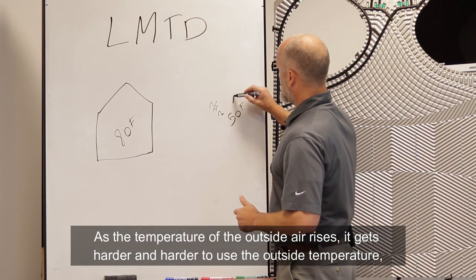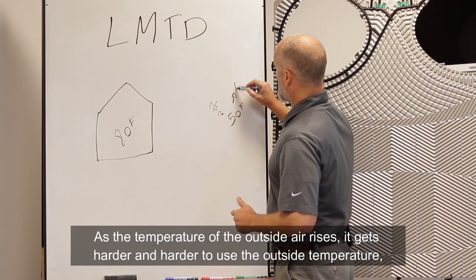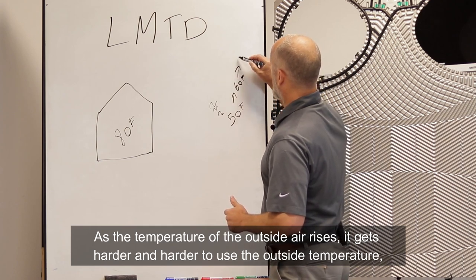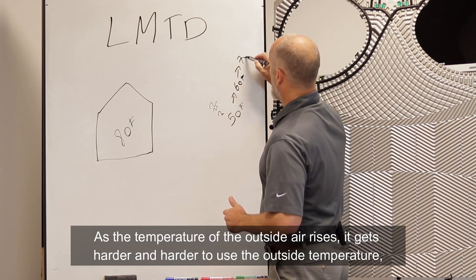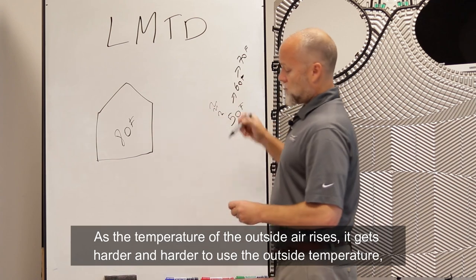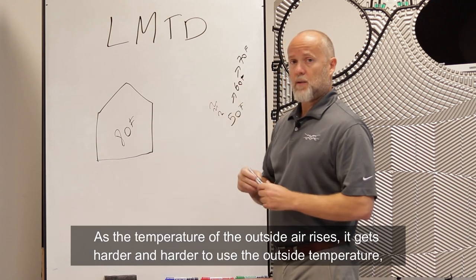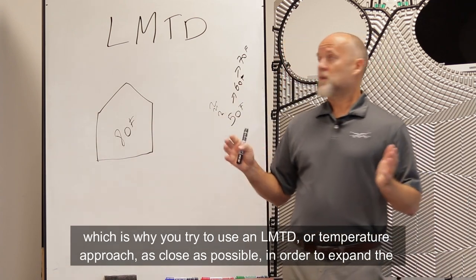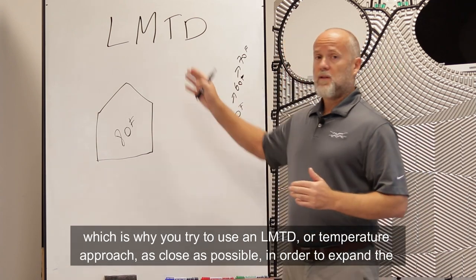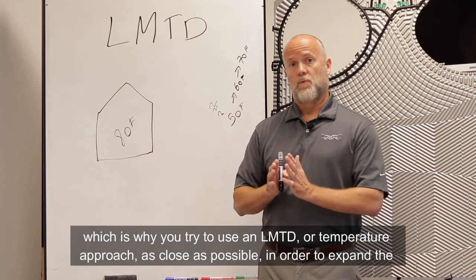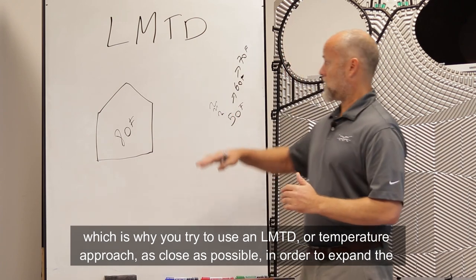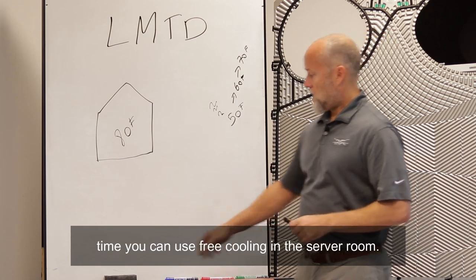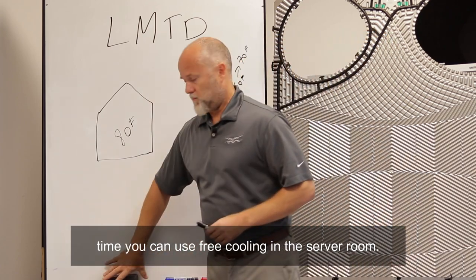As the temperature of the outside air rises, it gets harder and harder to use the outside temperature. That is the reason why normally you try to use an LMTD or a temperature approach as close as possible, in order to expand the time that you can use free cooling in the server room.